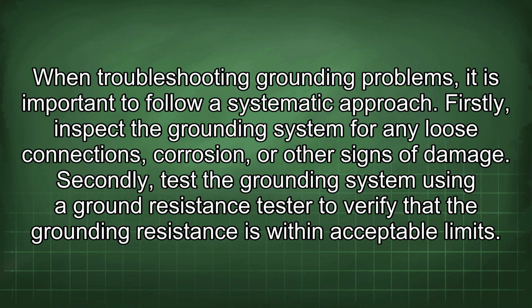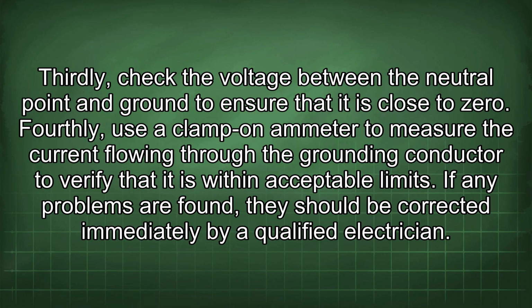When troubleshooting grounding problems, it is important to follow a systematic approach. Firstly, inspect the grounding system for any loose connections, corrosion, or other signs of damage. Secondly, test the grounding system using a ground resistance tester to verify that the grounding resistance is within acceptable limits. Thirdly, check the voltage between the neutral point and ground to ensure that it is close to zero. Fourthly, use a clamp-on ammeter to measure the current flowing through the grounding conductor to verify that it is within acceptable limits. If any problems are found, they should be corrected immediately by a qualified electrician.